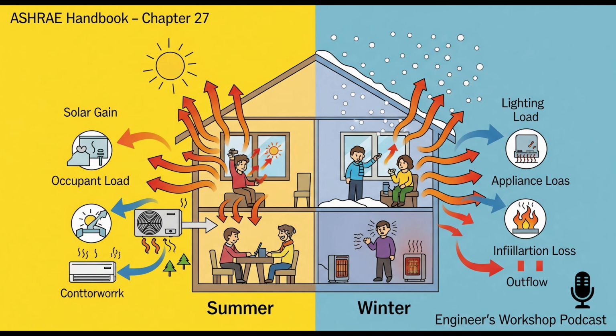For the cooling load, how much heat you need to remove, you're adding up all the ways heat gets in: through the walls, floors, ceilings, heat blasting through windows, heat from air leaks, and the smaller bits from people and appliances inside. The sources also talk about sensible heat, like just temperature, versus latent heat, the moisture, handling them separately - they're calculated distinctly.